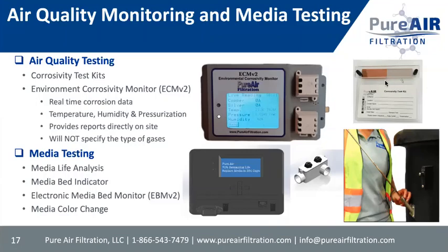It's doing what the coupon or corrosivity test kit does, but constantly and on a real-time basis, so that we're able to see and read what is the corrosivity environment in the room. And you can read here on the copper, the silver, we have 0 right now, which is great, but it could be G1, G2, G3, etc. It also tells us temperature, air pressure, and humidity, which are critical parameters for keeping the room non-corrosive. We'll talk about that in a second.